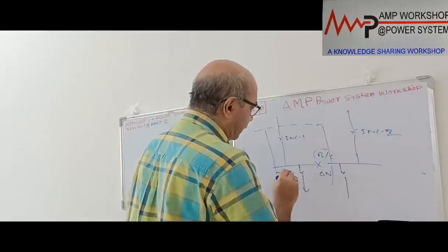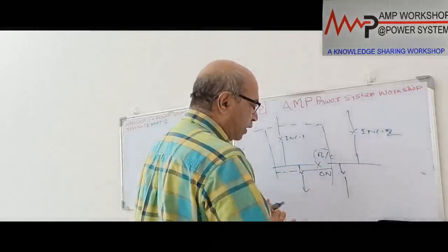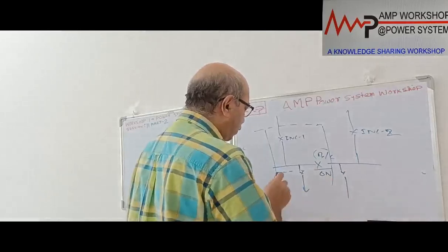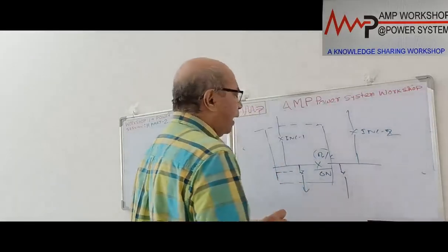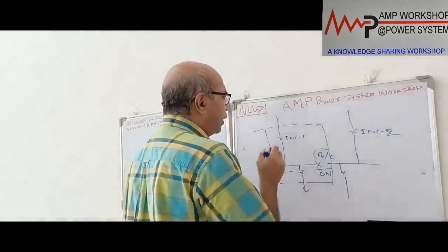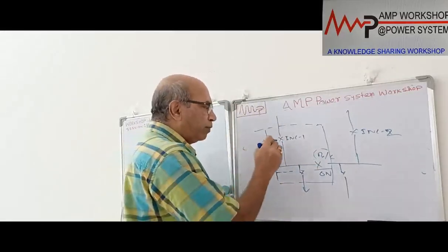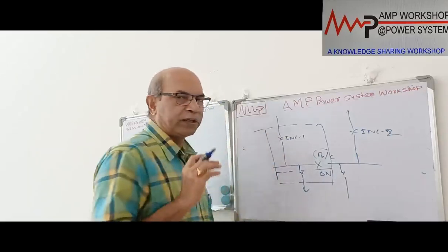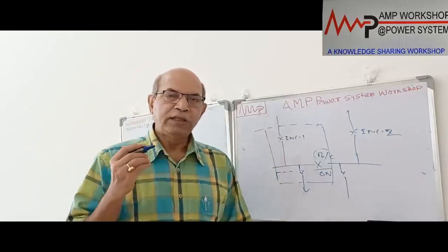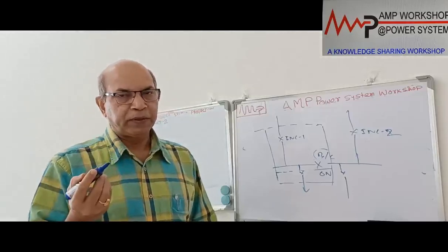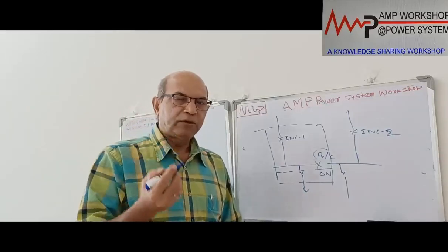When we are considering the busbar, or if you consider the outgoing feeder also to be included, then this will be one of the zones. And when we want to protect this zone, the protection system will be operating with the CT, so we have to place the CT in such a way. In normal practice for busbar protection, the CT on the source side will be located before the breaker, away from the busbar towards the source.